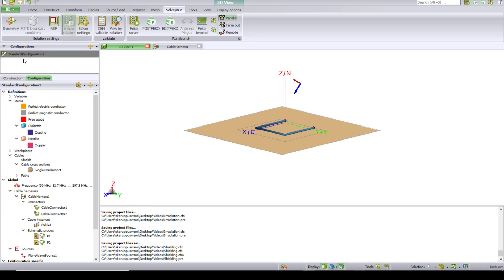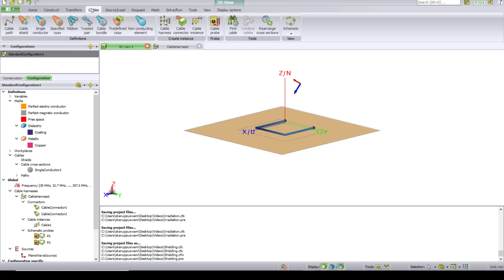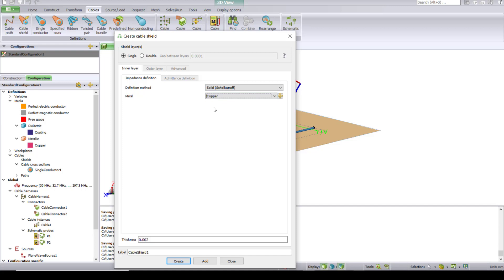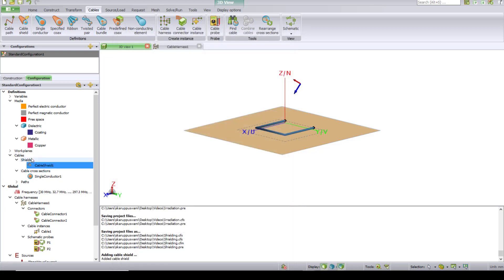The next step here is to first create a shield, for which you need to define a cable shield. Go under Cables and click on Cable Shield. There are different choices here: solid shield, braided shield, and you can even user-define the properties of a shield. But for this example, let's choose the solid shield with copper as a metal and let's choose a thickness of 0.1 and hit Create. This will create the cable shield under the Shields drop-down menu.